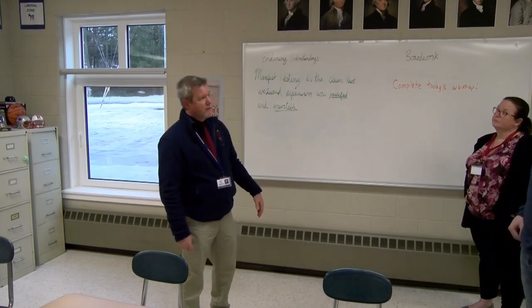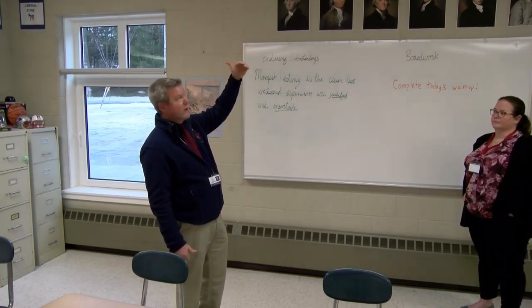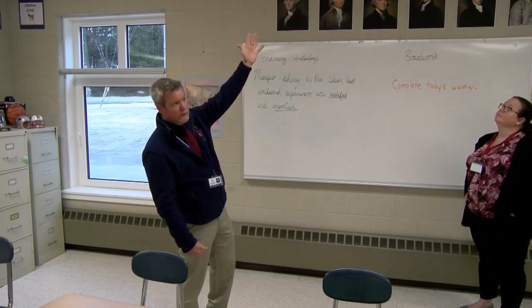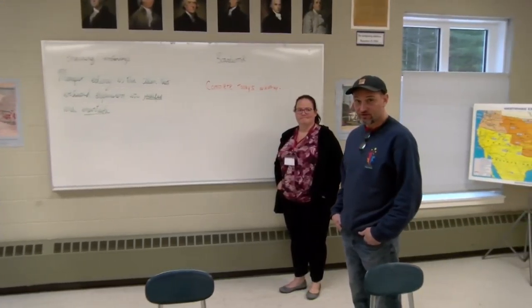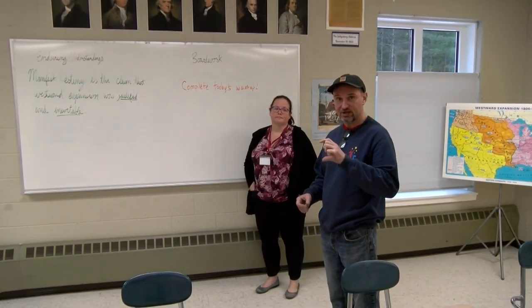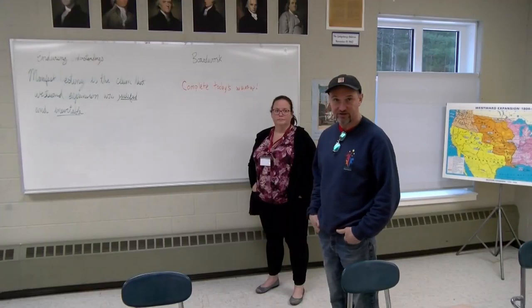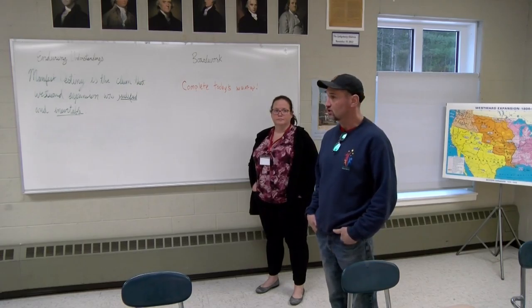The other major problem that we have is a similar problem that's occurring up at the ceiling. It's actually up at the roof, so it's above the ceiling at the roof level, and Dave will explain that for you. So we realized during the construction over the summer that that was never sealed. There's a 3-inch gap from the decking and the concrete block, 3-inch gap, and that goes all the way around the entire perimeter of the building as well. We want to seal that, we want to insulate it. There's a massive air leak there, which is a major heat loss and air conditioning loss as well.